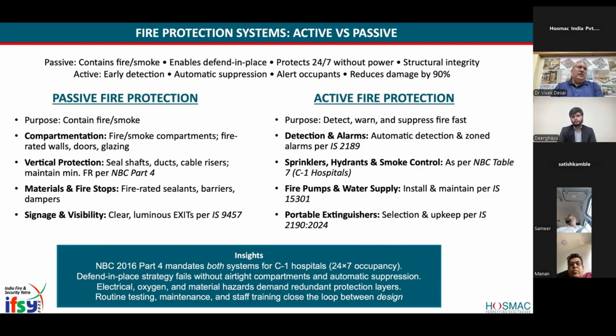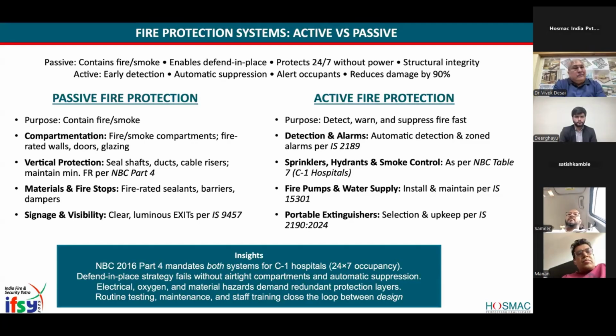If you create a building with too much glass, Satish will tell you that the glass becomes hot, and then it may actually splinter, and you may get hurt by the shards of glass. So Satish, how do you tackle that? Yeah, that's correct. Because the smoke contains certain high temperatures, people normally have longer facades with glass, which looks aesthetically good. But whenever fire is caught, smoke spreads, and smoke has a temperature. It transfers heat to the glass, and glass has a certain withstanding temperature. So after a particular temperature, glass will break.